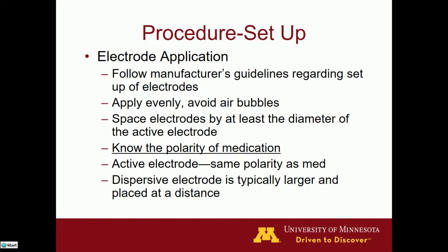You follow the manufacturer's guidelines regarding setup of electrodes. There is a video on Canvas that you can watch, and it goes through it real clearly. Again, we're going to talk about this in lab as well. What you do first is you put your medication on the active electrode, and if you have a dispersive electrode, some need saline, some are just a plain old dispersive electrode. Again, it depends on how they're manufactured.